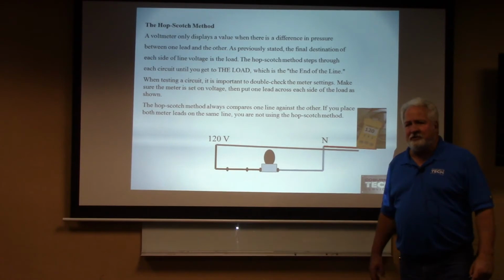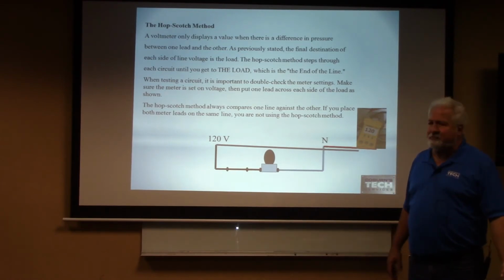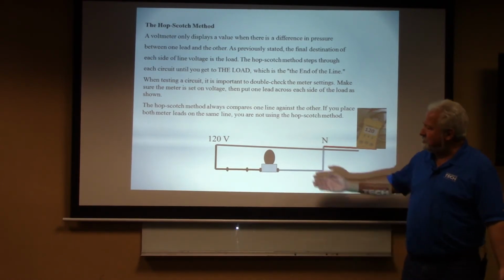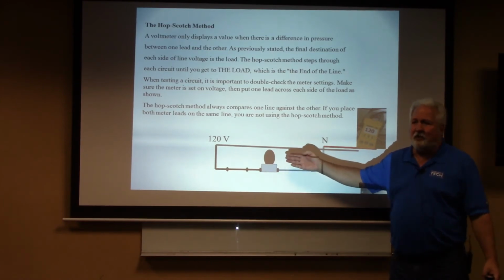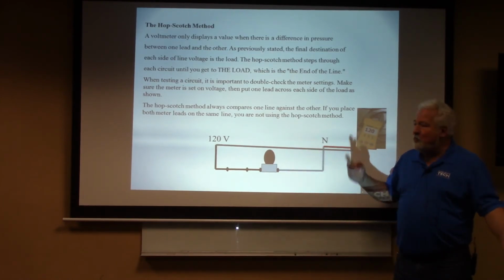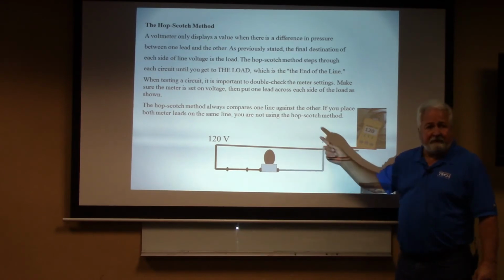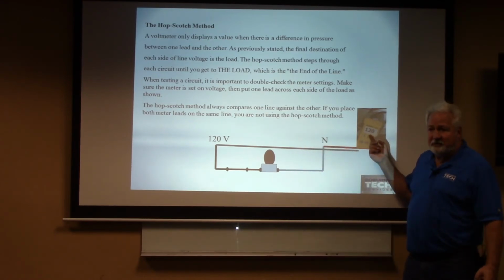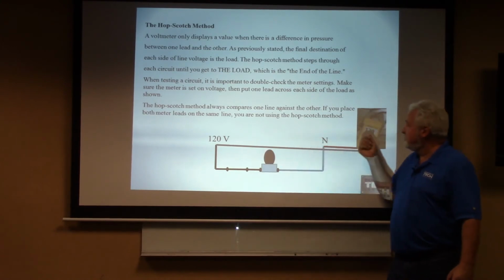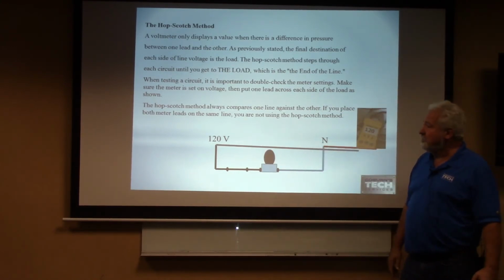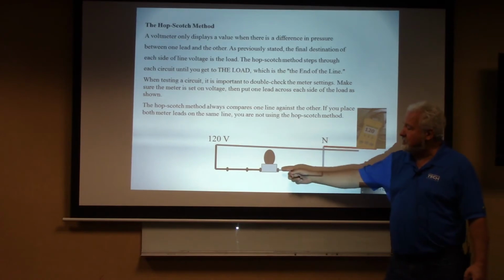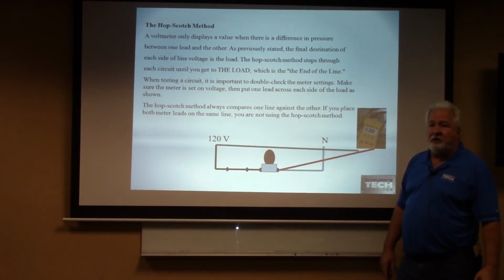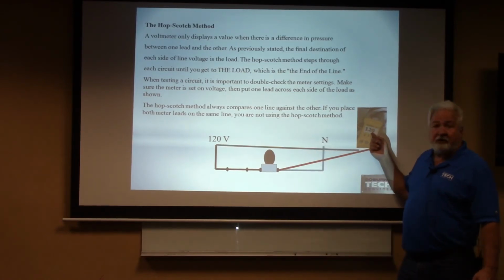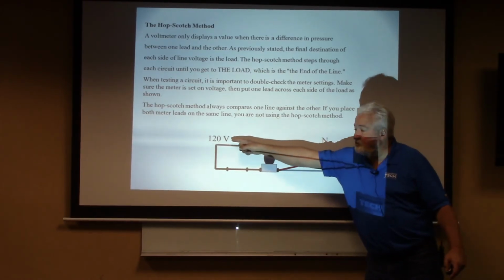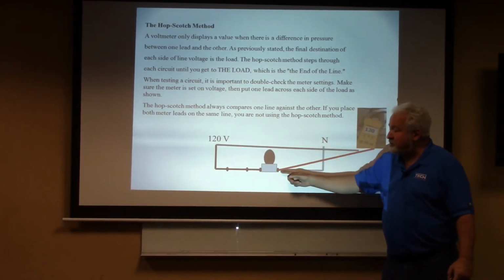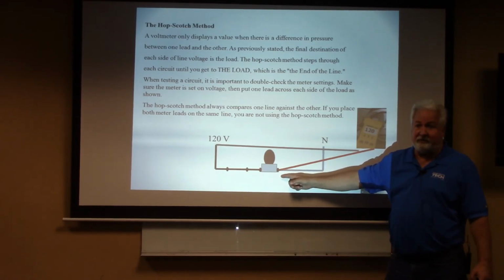One of the ways that I like to teach technicians to get started, and sometimes when a senior tech gets lost, I tell them to do the hopscotch method. The hopscotch method says, okay, my load is not working. Let's find out, number one, do I have source voltage? If I have source voltage, it's going to show up and say, yes, you have two different potentials on your meter. You've got 120 volt. I will take my neutral and slide it right to my load. From there, if I show that I have source voltage, I know that I have the 120 volt potential, and my neutral potential made it all the way to here.